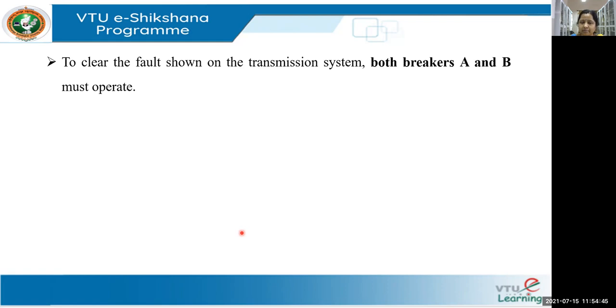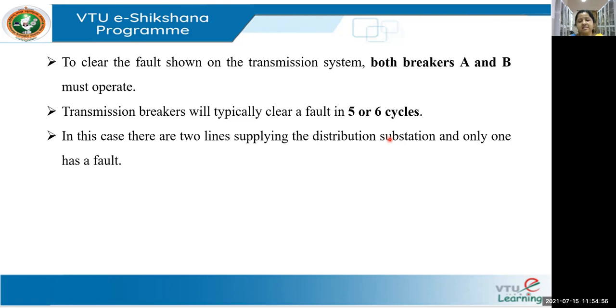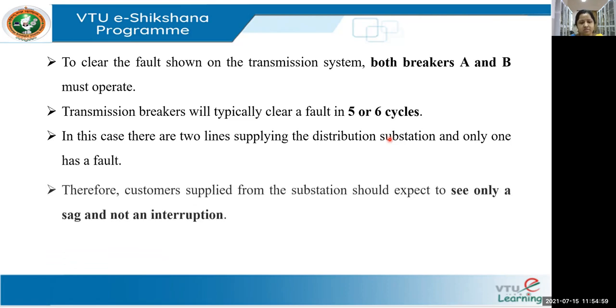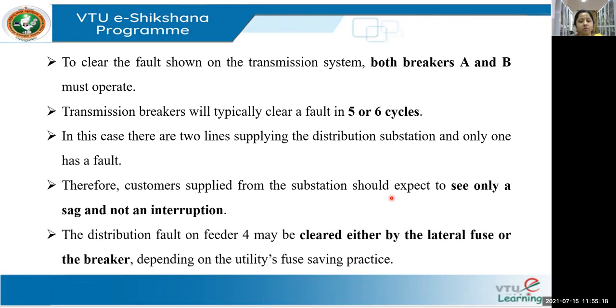If two lines are supplying the distribution system and one has a fault, the customer supplied from the substation should expect to see only a sag, not an interruption, as the second healthy line provides continuous supply. The distribution fault on feeder four may be cleared either by a breaker or by a fuse, depending on what practice the utility follows on a daily basis.